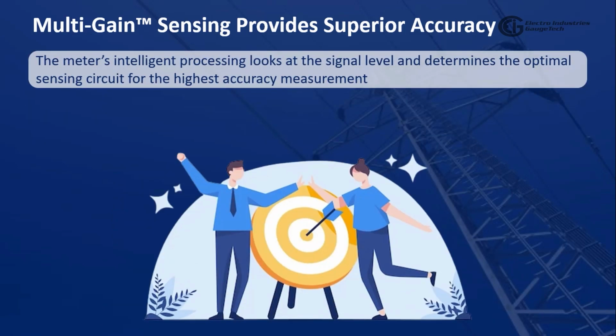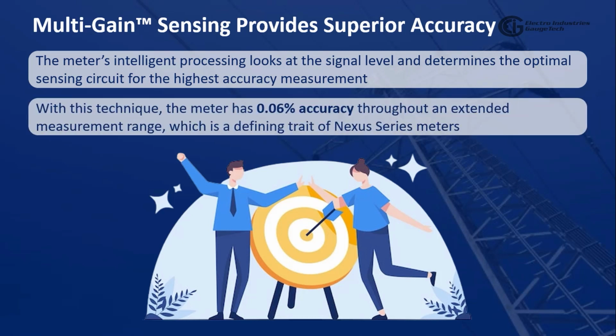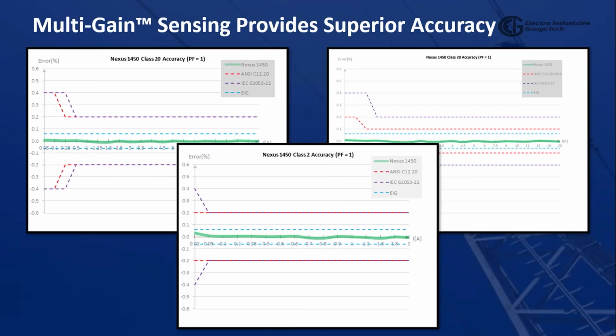The meter's intelligent processing looks at the signal level and determines the optimal sensing circuit for the highest accuracy measurement. With this technique, the meter has 0.06% accuracy throughout an extended measurement range, which is a defining trait of Nexus series meters. The images here show the typical accuracy charts for Nexus 1450 meter.